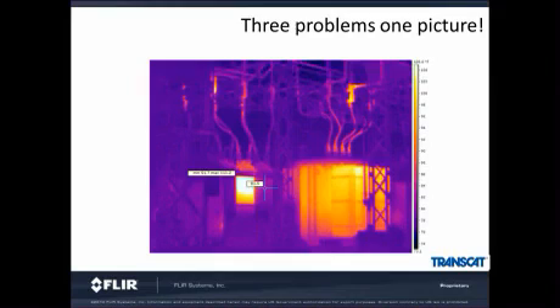Inside a substation, there are many targets to look at with a thermal camera. For example, in this picture, we see three separate problems. The first problem is the oil-filled circuit breaker. We can see the center one is warmer than the other two tanks. They should all be the same temperature. Since the oil acts like an insulator, the object inside has to be really hot to warm up the oil this much. There is a lot of oil in these tanks, and it takes a lot of energy for the camera to measure about 30 degrees warmer from one tank to the other.